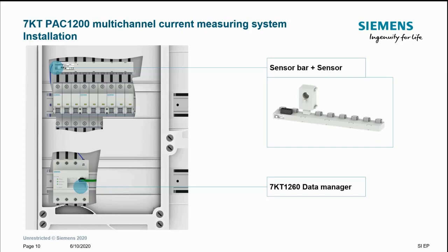Effectively, the kit consists of 3 components: the sensor, which sits around the outgoing cable; the sensor bar, which is what all the sensors mount onto and collect the measured data through RS-485 Modbus RTU connections; and the third and final component, the data manager, to which the measured data is sent.